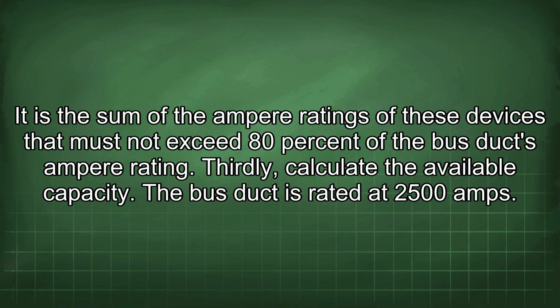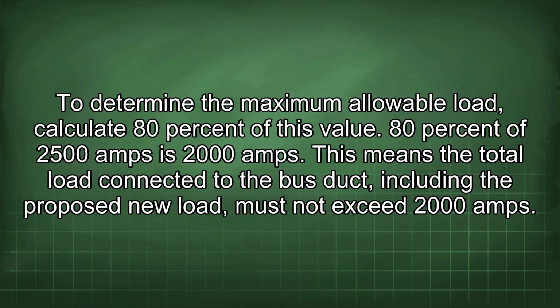Thirdly, calculate the available capacity. The bus duct is rated at 2500 amps. To determine the maximum allowable load, calculate 80% of this value. 80% of 2500 amps is 2000 amps. This means the total load connected to the bus duct, including the proposed new load, must not exceed 2000 amps.